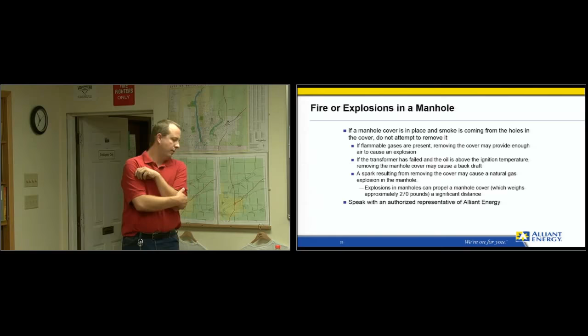Flammable gases are present. Remove the cover and provide enough air, and you can cause an explosion. So removing that cover is sometimes worse than just leaving it be. If you have a transformer that's failed and the oil is above the ignition temperature, removing the manhole cover may cause a backdraft. And the spark resulting from removing the cover may ignite natural gas. If that happens, it's not your day, that's for sure. An explosion of a manhole can propel a manhole cover, which weighs about 270 pounds, a significant distance.